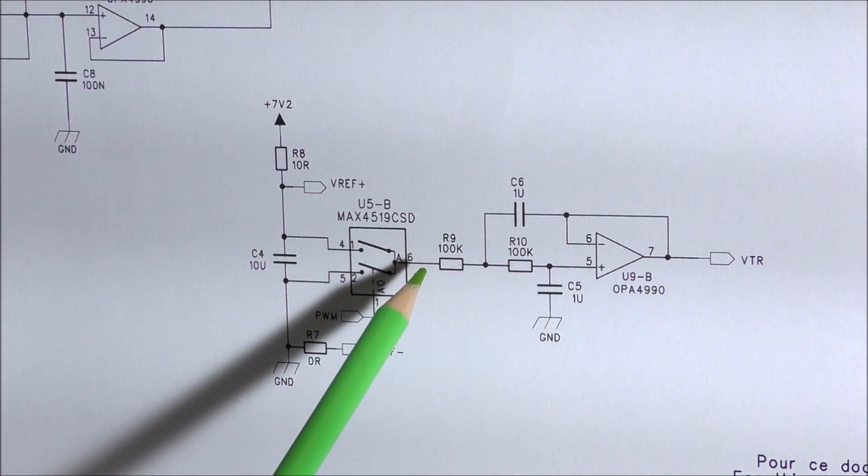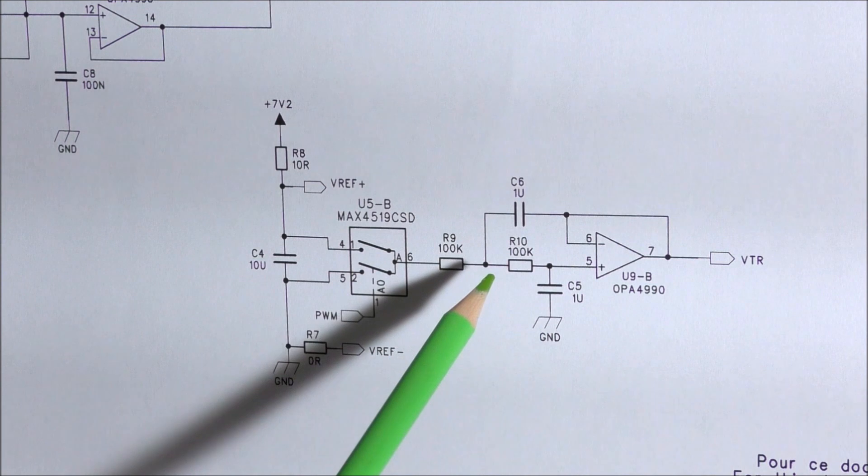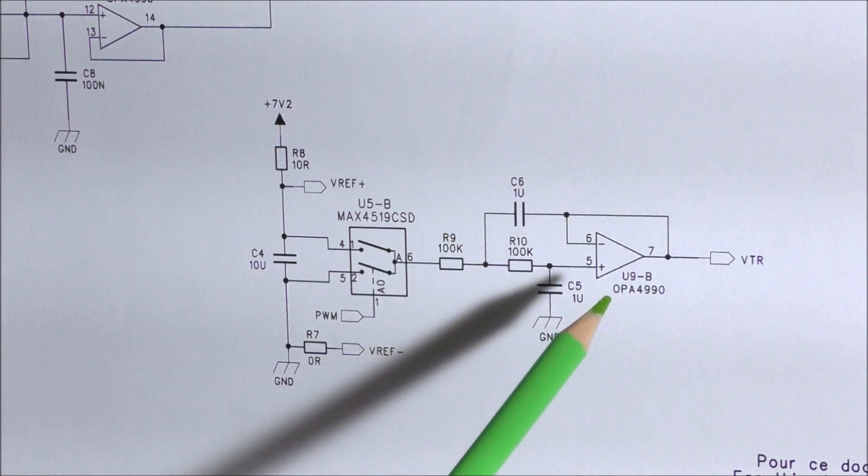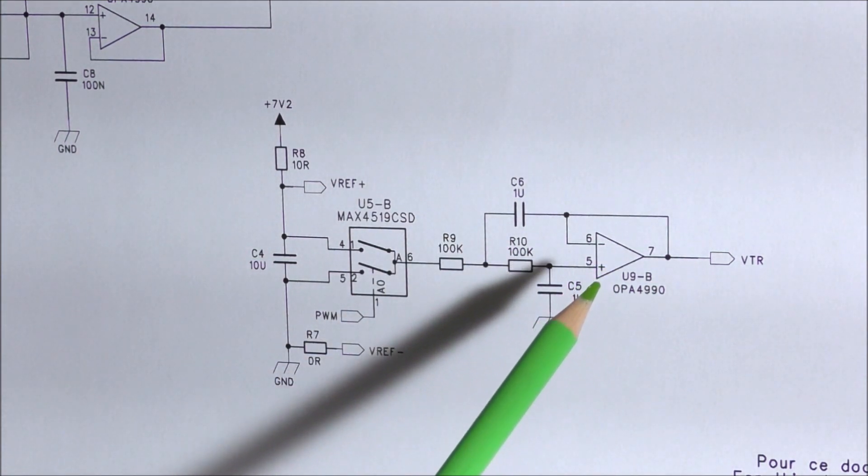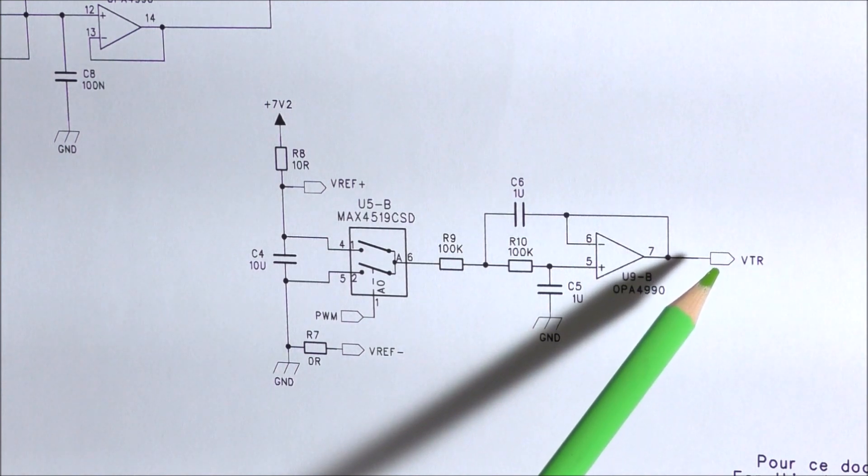And this signal is fed to a second order low-pass filter, which uses these two resistors, these two capacitors, and also this op-amp here. And this signal is fed to the servo control, which permits to set the total temperature probe resistance.